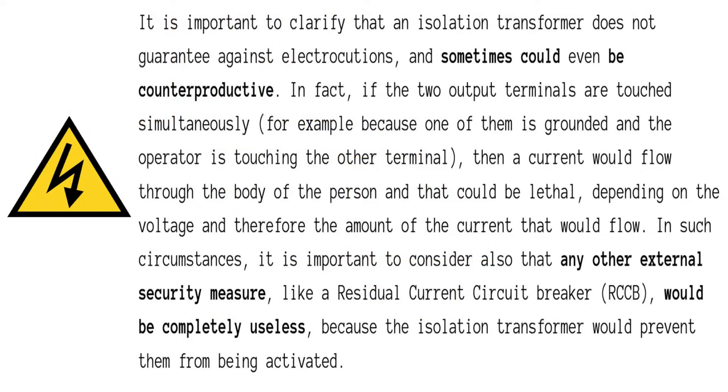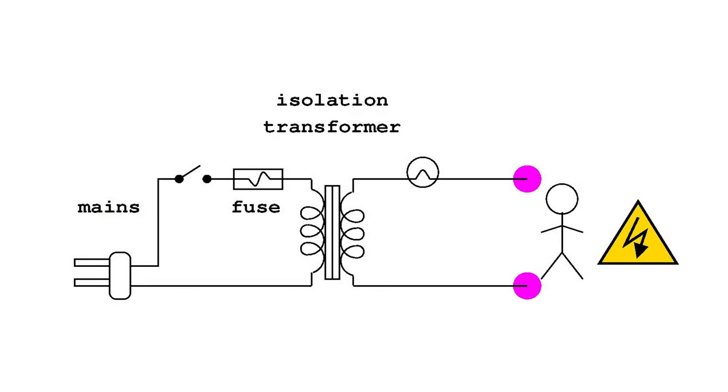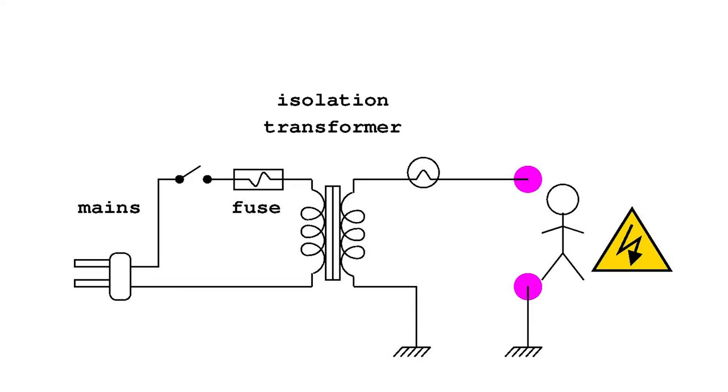However, it is important to clarify that an isolation transformer does not guarantee against electrocutions and sometimes it could even be counterproductive. In fact, if the two output terminals are touched simultaneously, for example because one of them is grounded and the operator is touching the other terminal, then a current would flow through the body of the person and that could be lethal depending on the voltage and therefore the amount of the current that would flow.